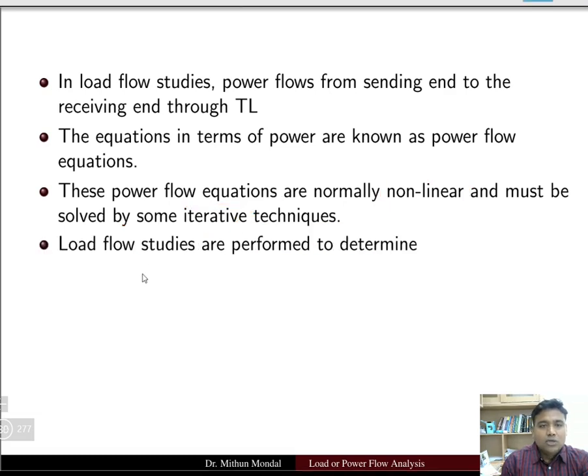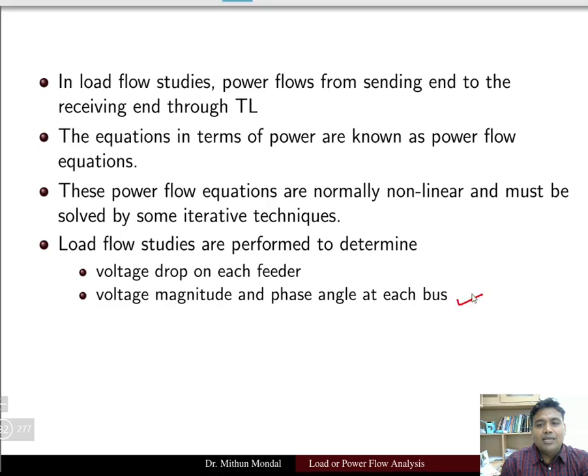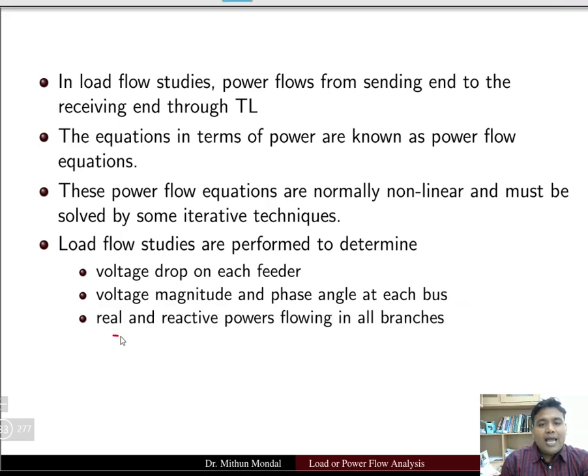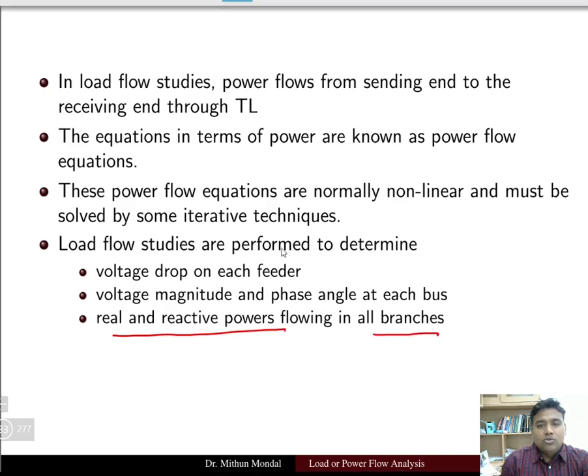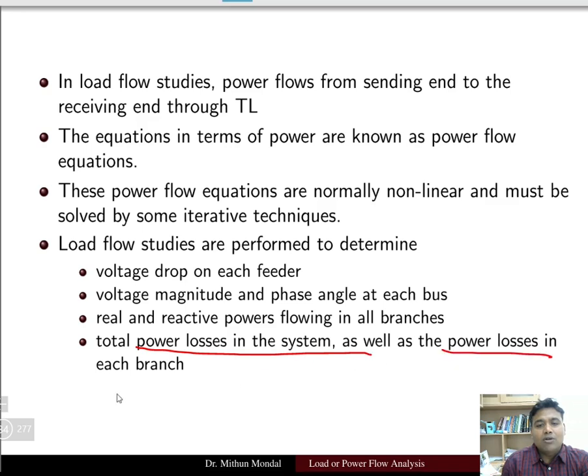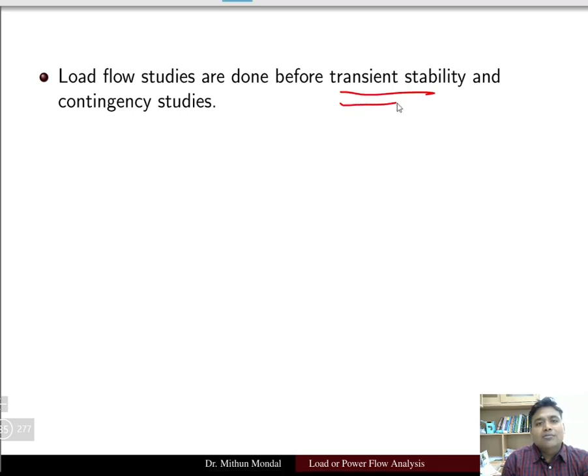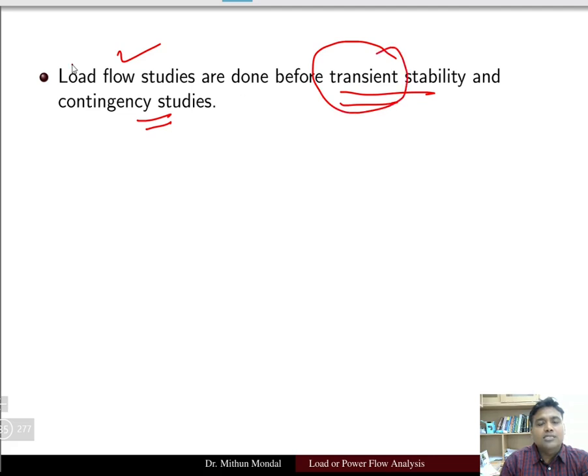Load flow studies are performed to determine: the voltage drop on each feeder; the voltage magnitude and phase angle at each bus; the real and reactive power flowing in all branches; and the total power loss in the system as well as power losses in each branch. Load flow studies are done before transient stability and contingency studies, as they are only for obtaining the steady state solution.